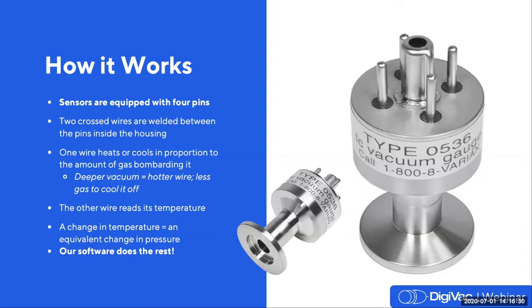So more air molecules, or a pressure closer to atmospheric, surrounding the filament will transfer the heat away faster, while fewer molecules to diffuse the gas, at a deeper vacuum for instance, will keep the wire hotter. Then the other filament takes the first one's temperature, and our software interprets that change in temperature as an equivalent change in pressure, turning it into a reading that anyone can understand, and our software does the rest.